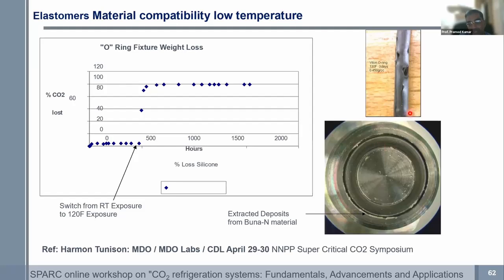We have had first-hand experience where all of a sudden there are O-ring failures in multiple places. There is a phenomenon called explosive decompression, where carbon dioxide at high pressure will dissolve into the polymer, the elastomer inside the O-ring. And once it's depressurized, it will just come out at supersonic speeds, causing small blisters on the O-ring. So this is one of the issues that are typically faced. New materials are being invented that can actually withstand this kind of explosive decompression.